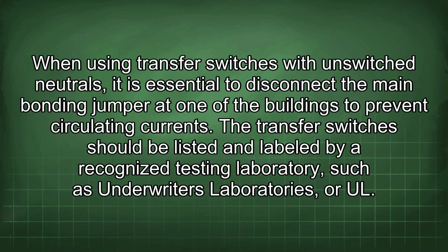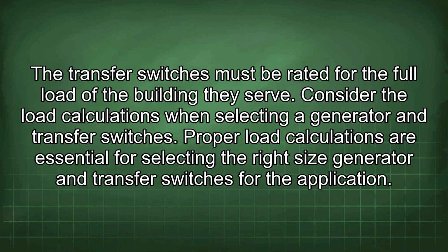When using transfer switches with unswitched neutrals, it is essential to disconnect the main bonding jumper at one of the buildings to prevent circulating currents. The transfer switches should be listed and labeled by a recognized testing laboratory such as Underwriters Laboratories, or UL. The transfer switches must be rated for the full load of the building they serve. Consider the load calculations when selecting a generator and transfer switches. Proper load calculations are essential for selecting the right size generator and transfer switches for the application.